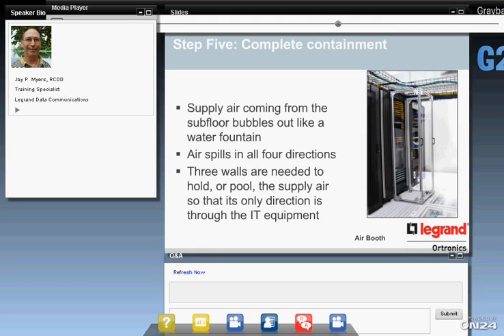So for this, to focus right on that, we can put a portable containment booth. It's just a 3-sided phone booth on wheels, and put it right up against the front of the rack, so the cold air coming up out of the perforated tile inside there just fills right up. Keeps concentrated cooling. It allows you to use the entire rack all the way up to the top. The standard one of this is 24 inches wide, but we can make them 48 or even 6 feet wide.